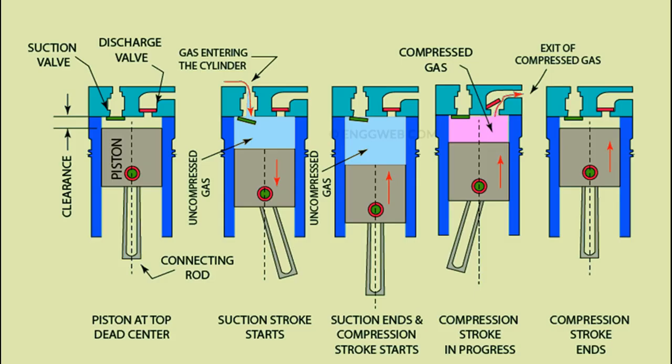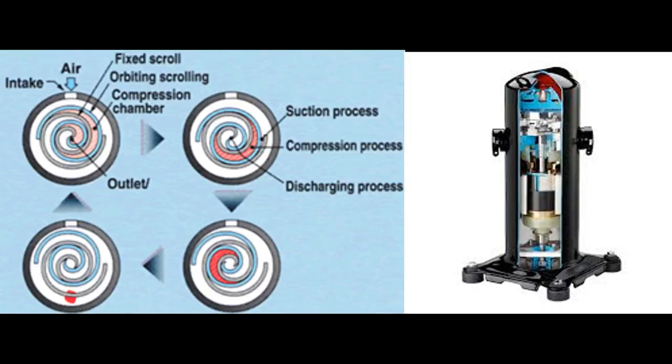A reciprocating compressor works by moving a piston in a cylinder via a connecting rod and crankshaft. If only one side of the piston is used for compression, it is described as single acting. If both sides of the piston — top and underside — are employed during the up and down stroke, it is defined as double acting. A scroll compressor has one fixed scroll which remains stationary and another moving or orbiting scroll that rotates through the use of a swing link, slowly pushing pockets of refrigerant toward the center, reducing the volume of the gas.